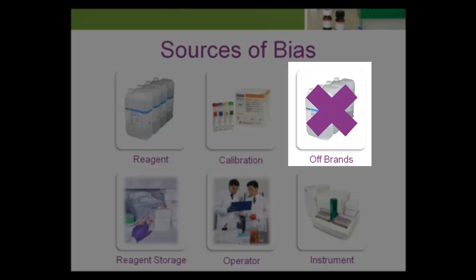Recalibrating more often than recommended by the manufacturer can point to a problem in the test system, or due to a process control system that's inappropriate for the test and is producing false error flags. Another source of bias is off-brand reagents, calibrators, or consumables. These can be substandard to manufacturer ones. For example, a cuvette provided by the manufacturer could have more consistent optical quality than an off-brand cuvette.